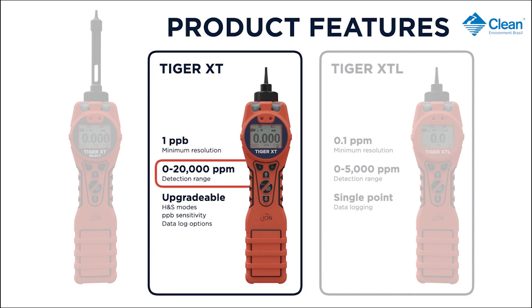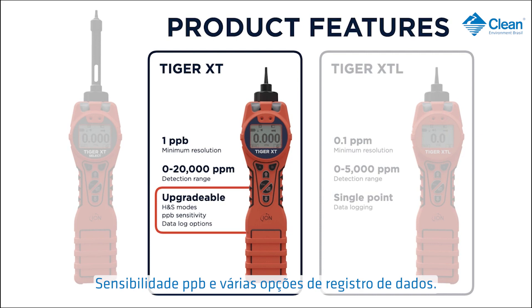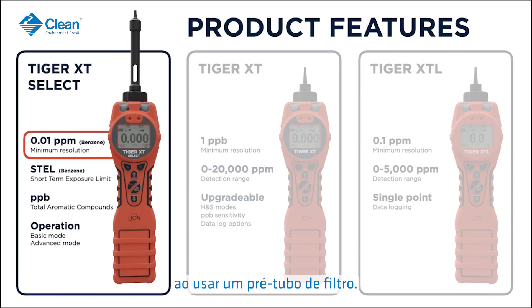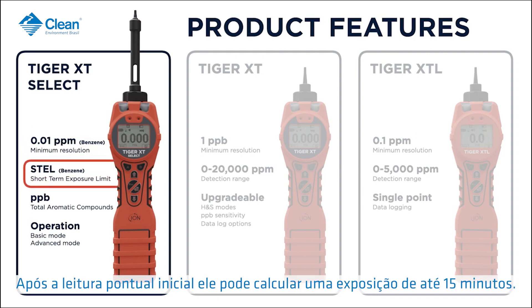Tiger XT's upgradable features include health and safety mode, ppb sensitivity, and various data logging options. Tiger XT Select can detect benzene specifically down to 0.01 ppm when using a pre-filter tube. After the initial spot reading, it can calculate a 15-minute STEL.